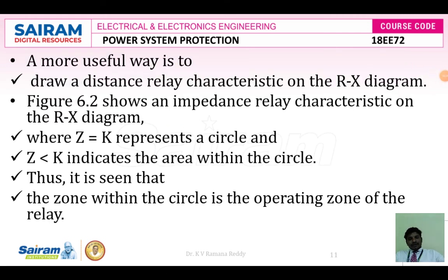Therefore, the relay will function whenever the fault lies within the operating region, when the K value is greater than the impedance value.